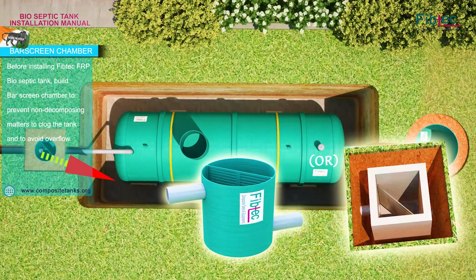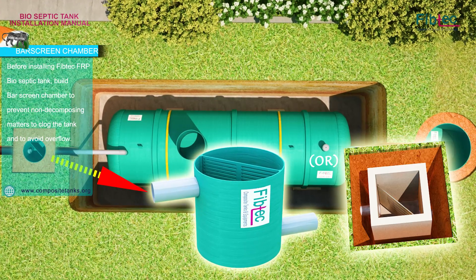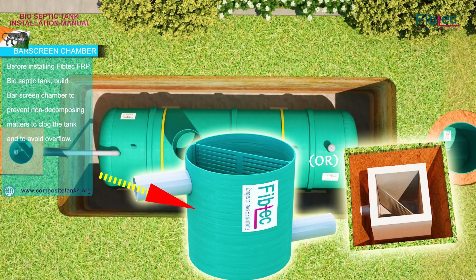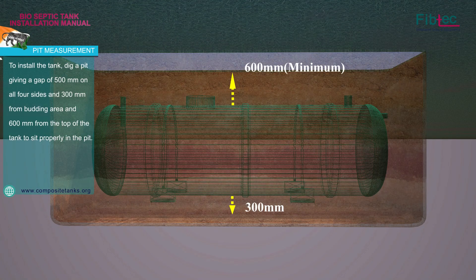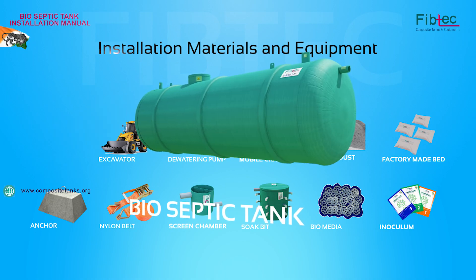Before installing the Fibtec FRP Bio-Septic Tank, build a bar-screen chamber to prevent non-decomposing matter from clogging the tank and causing overflow. To install the tank, dig a bigger pit giving a gap of 500 mm on all 4 sides, 300 mm from the bedding area, and 600 mm from the top of the tank to sit properly in the pit.